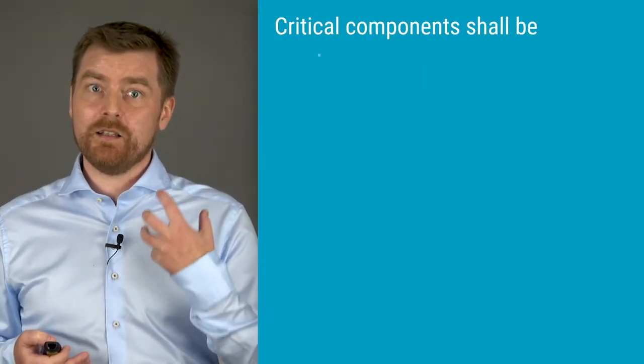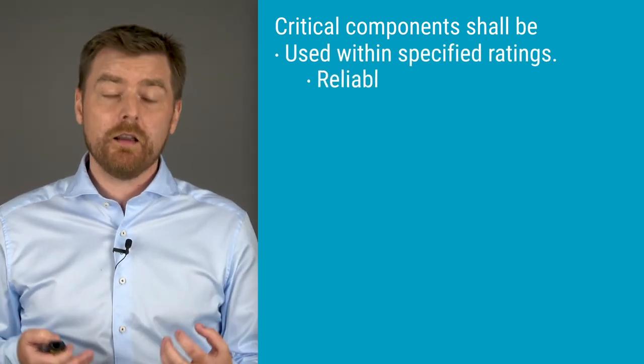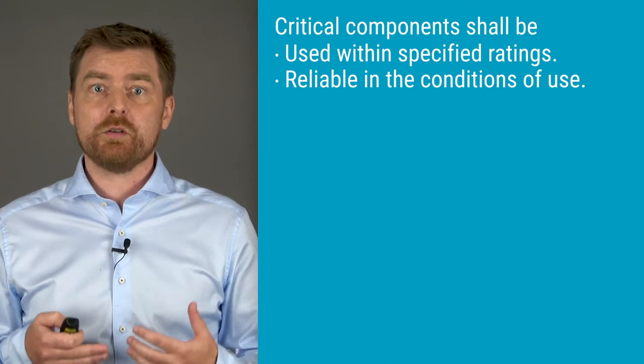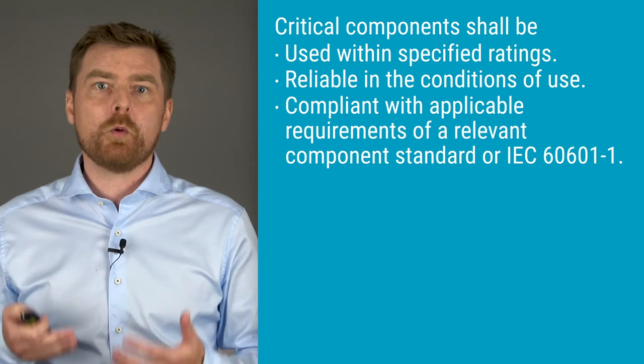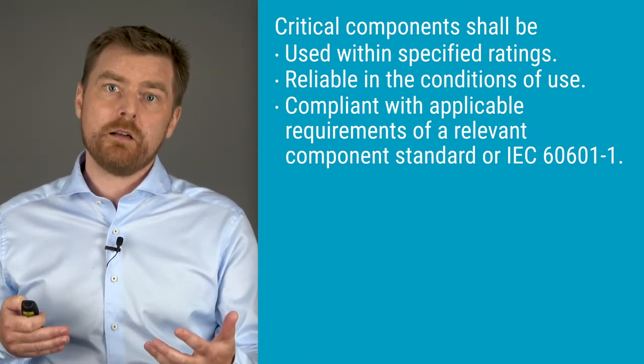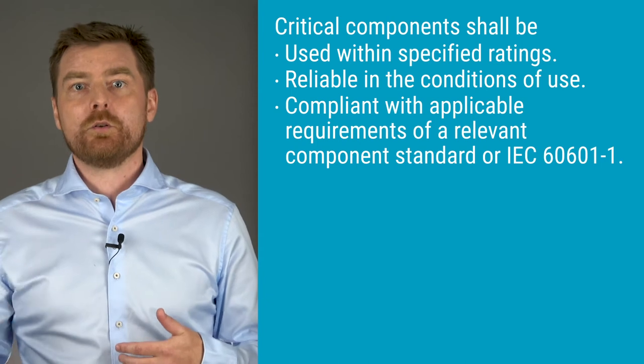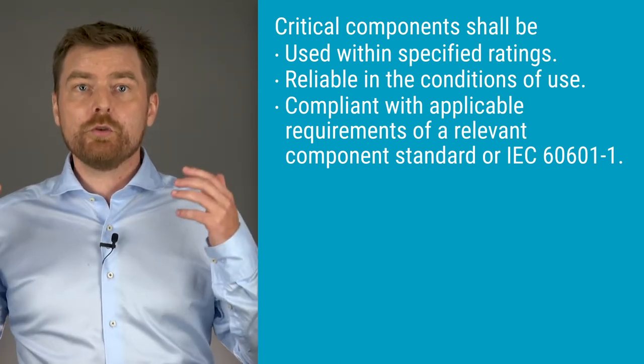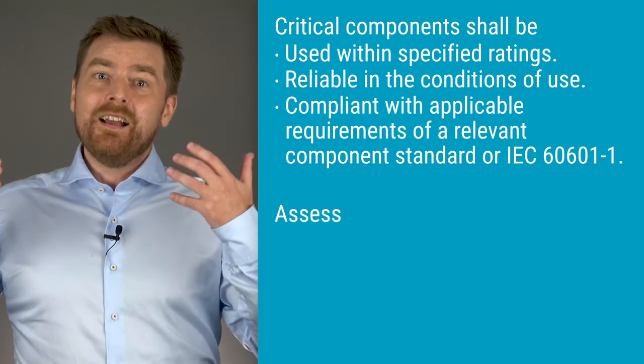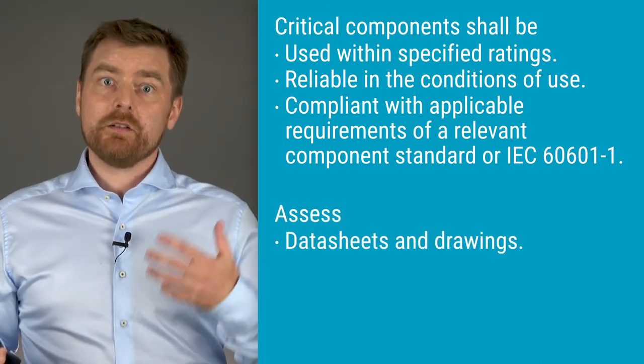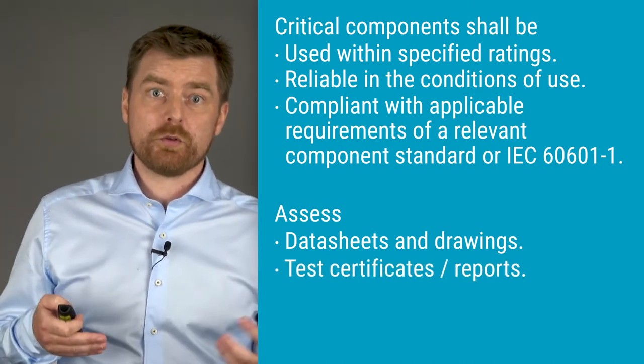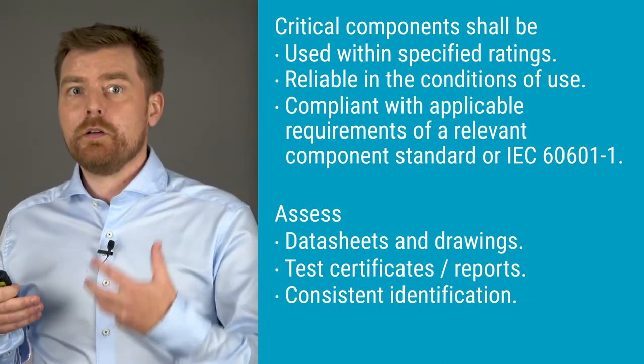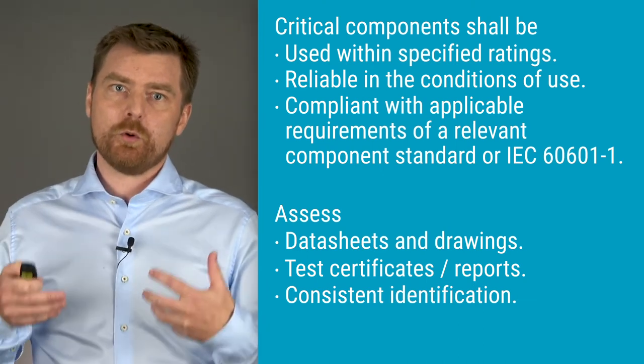The requirements for critical components are that they shall be used within their specified ratings, they shall be reliable in the conditions of use in the device, and they shall comply with applicable requirements of either a relevant component standard or IEC 60601-1. To check compliance with the requirements, you shall assess data sheets and drawings from the manufacturer, the test certificates or test reports, and that the component is consistently identified across all documentation.